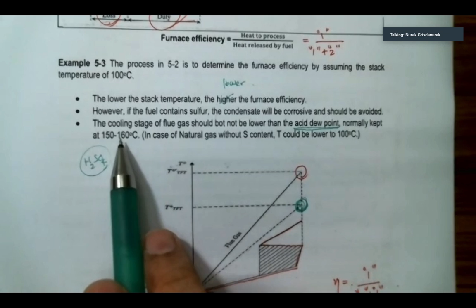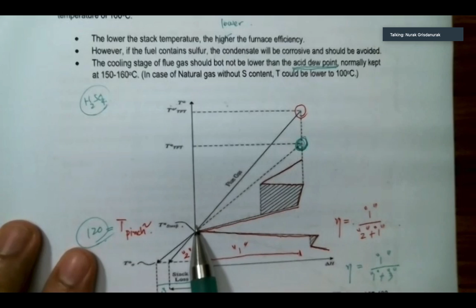when the temperature is below 150 to 160 degrees Celsius. So you cannot have the set point lower than 160 degrees Celsius, even though the pinch point equals 120. Even though the pinch point equals 120, if you have sulfur in the fuel oil, you have to pass to 160 degrees Celsius, not 120 degrees Celsius.